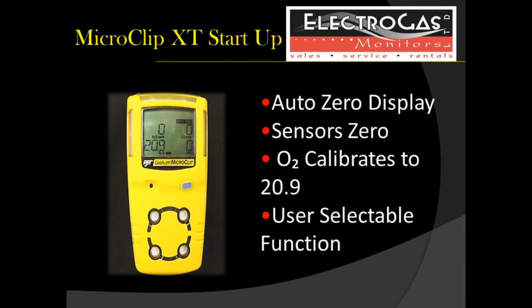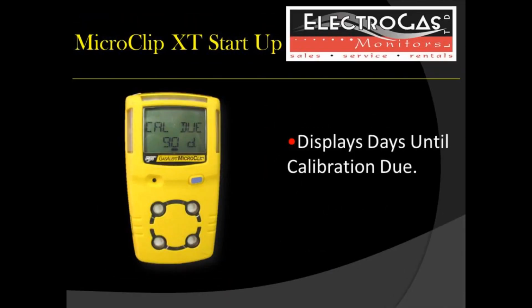After the initial tests, your monitor will perform an auto zero. The oxygen sensor will be set to 20.9 and all other sensors will be set to 0. Be sure that you are in a fresh air environment free of other gases and toxins while performing this function. The monitor will then display the number of days until the next calibration is due. If calibration is past due, the monitor will say so.